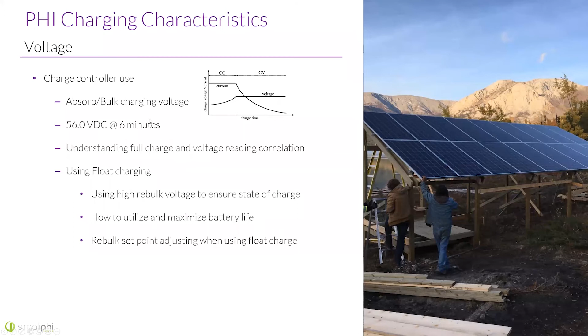I'm just going to speak in 48 volt terms, by the way. You can always divide if you need 12 or 24. But float charge is totally okay when it comes to DC coupled, maybe a grid tie or a solar array or something like that. Now, if it's an inverter charger, you can set it a little bit lower. This is kind of changing right now. You can charge at 54.4 volts on the absorb and the bulk at 1 hour instead of the 6 minutes that we were doing here. That's really low.